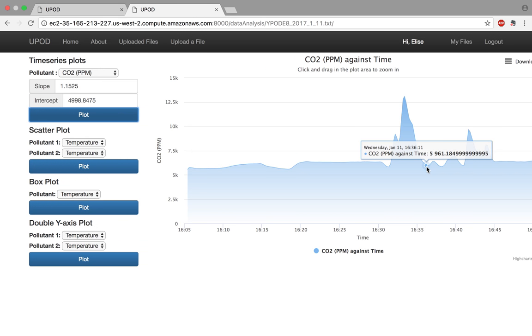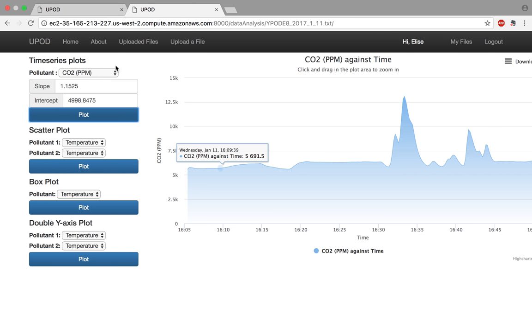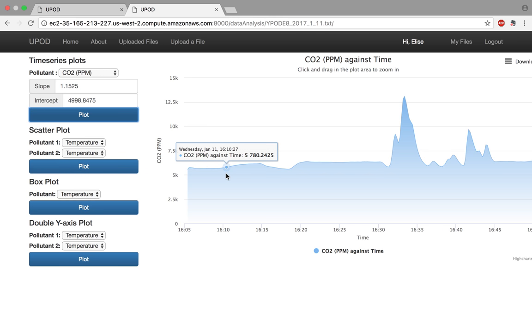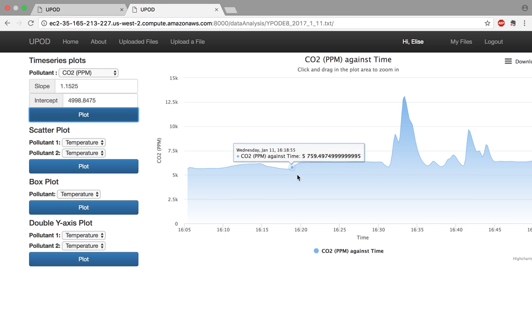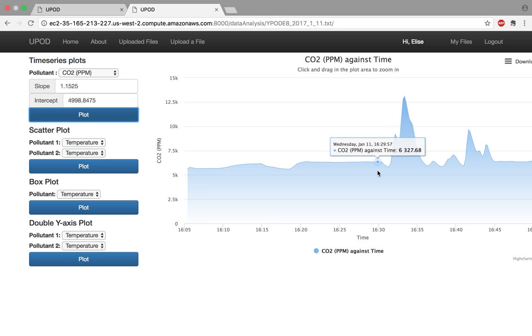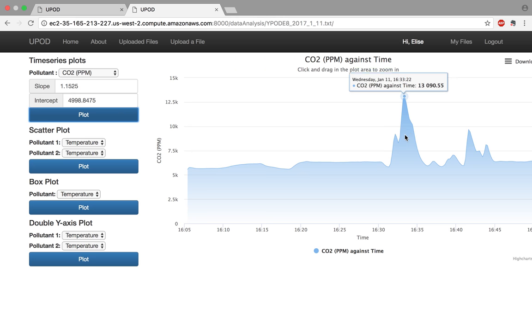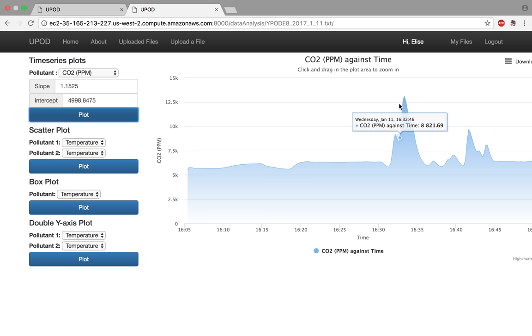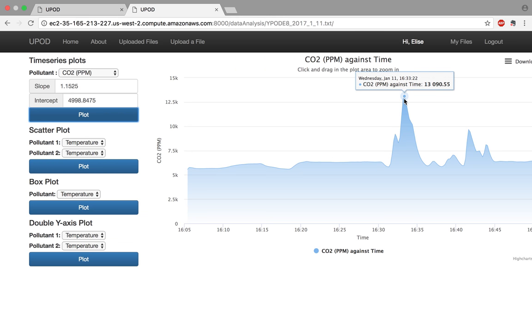And so by using the carbon dioxide parts per million plotter tool, we can create a plot in units of concentration to say that at 16 hours and 33 minutes on Wednesday, January 11th, we have approximately a concentration of 13,090 parts per million of carbon dioxide exposed to the pod.